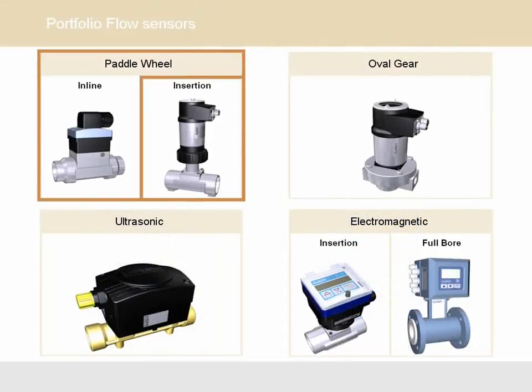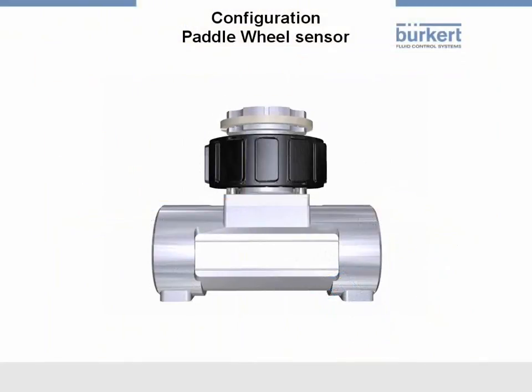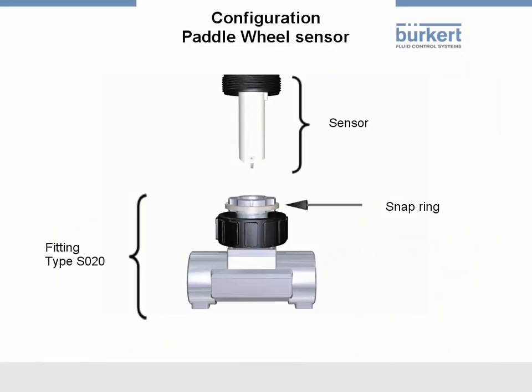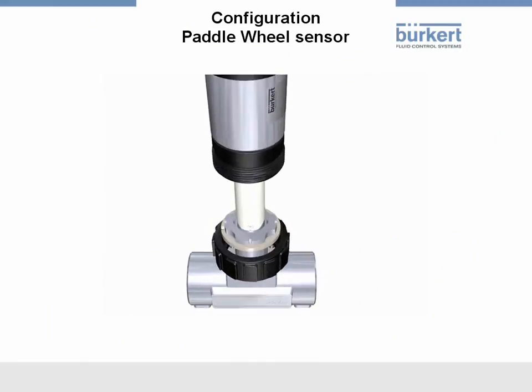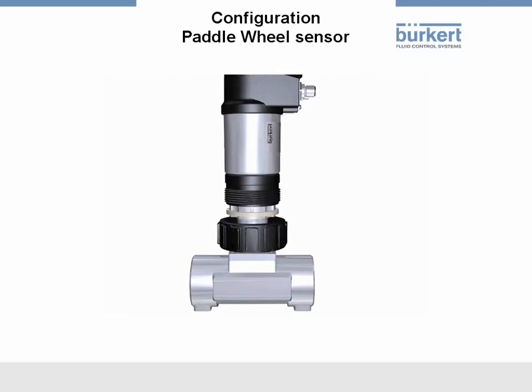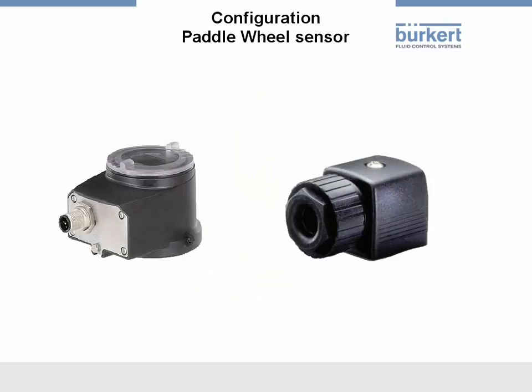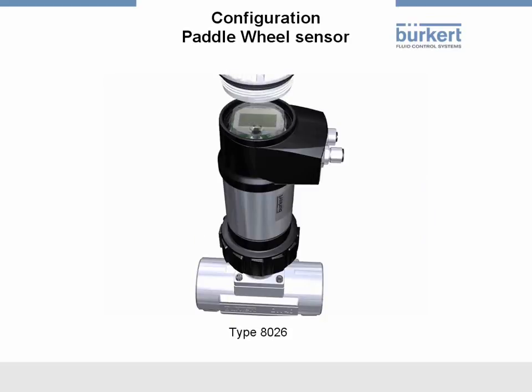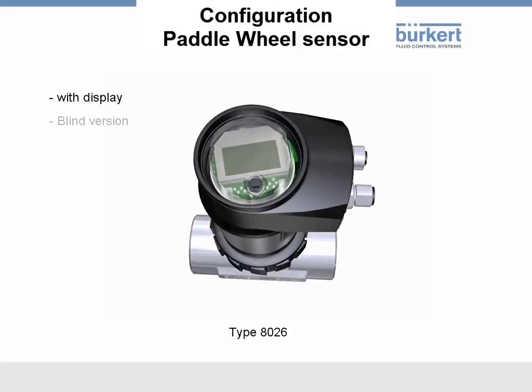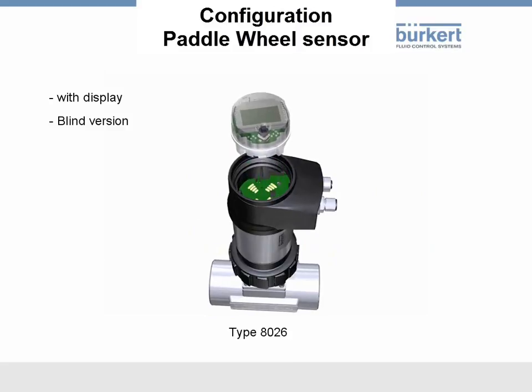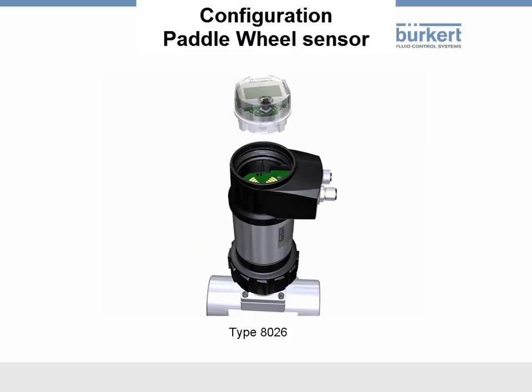Now we come to paddle wheel insertion. For the insertion model, a different fitting is used, which is equipped with a neck attachment for mounting of the sensor, which consists of a finger and the paddle wheel on the bottom end of the finger. In this version, the compact unit is screwed together with the fitting. The electrical connection of the electronics is available via an M12 connector or a cable gland. Depending on the application, it's possible to use models with a display and function keys or blind versions without a display and function keys. The easily extractable display, which includes upload and download capability, can be used for several different models.